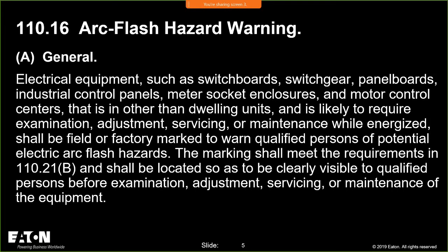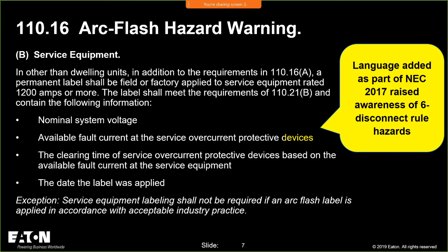And 110.16 is the arc flash hazard warning. That's typically the warning we would have on a piece of equipment. That's the generic warning, but now we have additional requirements in 110.16(B) that say you have to label it with the nominal system voltage and the available fault current at the service overcurrent protective devices. You'll notice that it doesn't say the service overcurrent protective device. It says devices, right? And it says devices for a reason, because you could have 6 disconnects there. And obviously you could have six separate disconnects as well. But again, that's going to be impacted, because you're not going to have a single panel board with 6 disconnects on it.